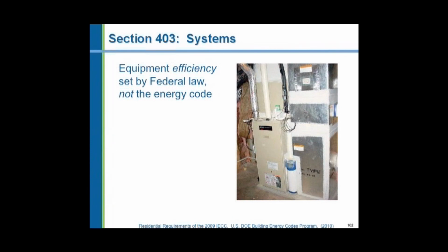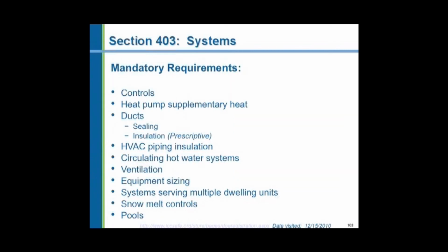For furnaces, air conditioners, and water heaters, we defer to the federal laws. The efficiencies of furnaces are minimum 80% combustion efficiency for heating, 13 SEER for cooling, and for water heaters, an energy factor, as it's referred to, of 0.62. The MUEC mentions nothing about this. Section 403 of the Energy Code refers to mechanical equipment, and there are certain mandatory requirements. And here's the list of them: temperature controls, heat pumps, air supply and return ductwork, HVAC piping insulation, circulating hot water systems, ventilation, sizing equipment, multiple dwelling units, snow melting, and swimming pools.